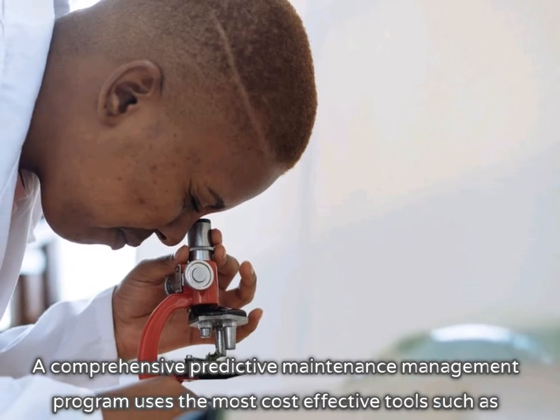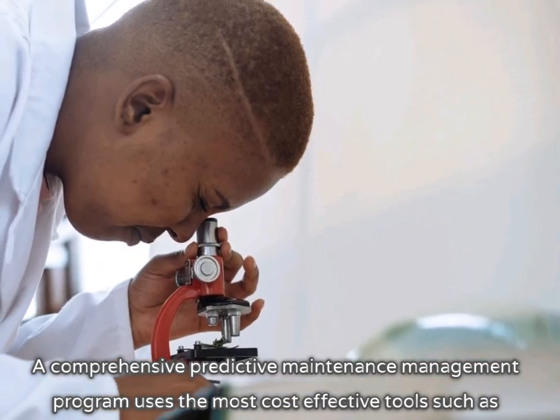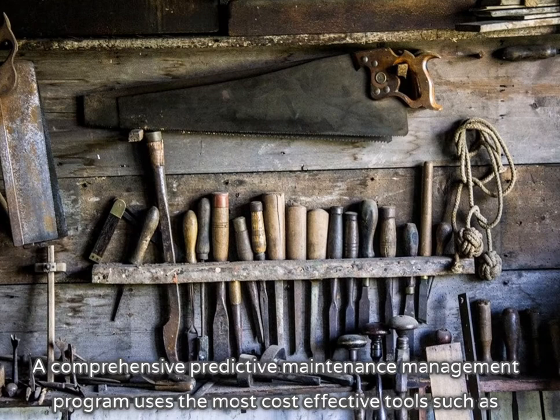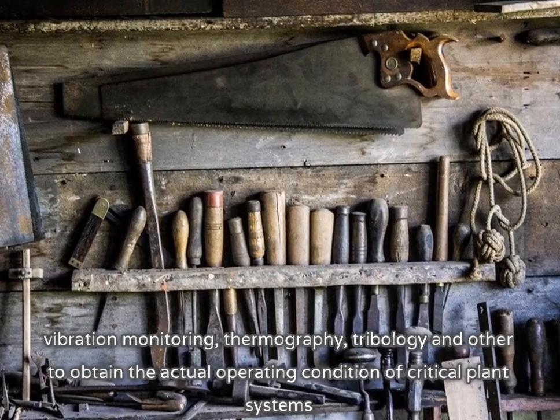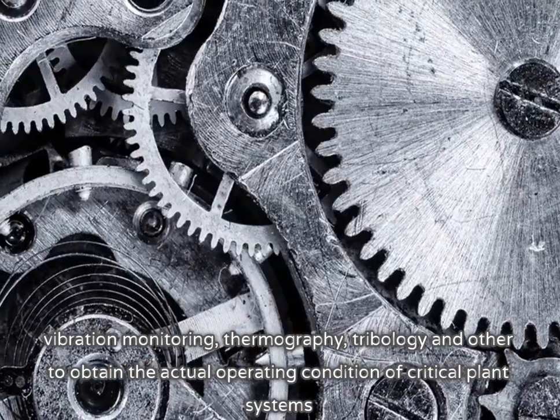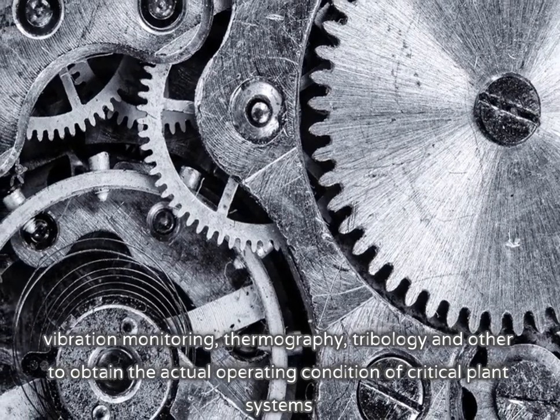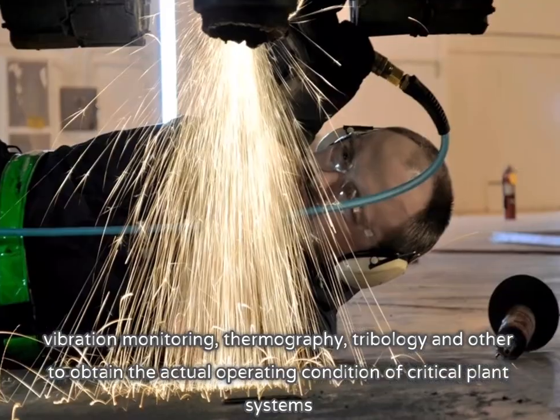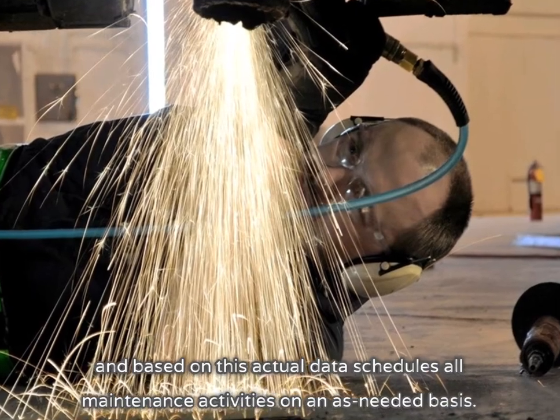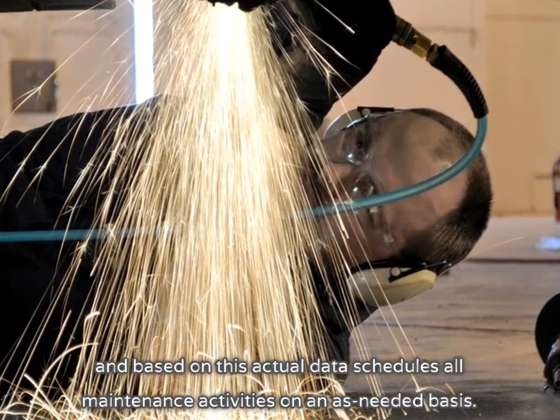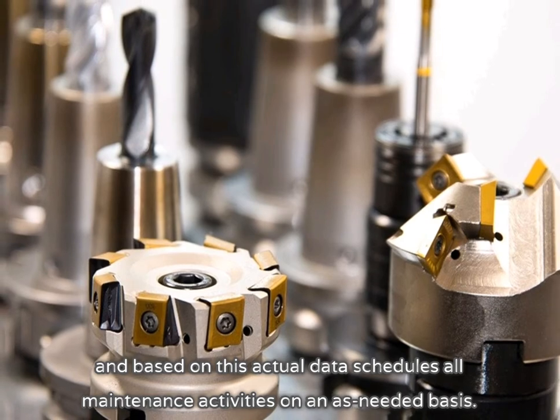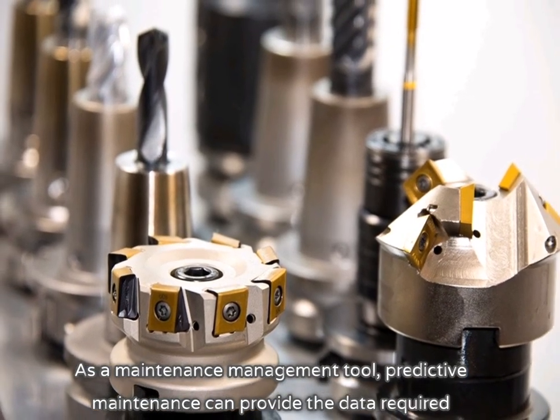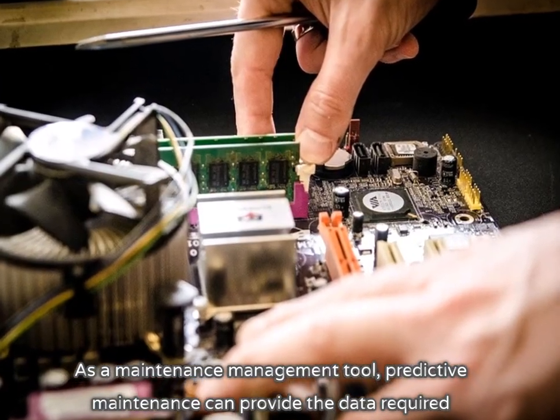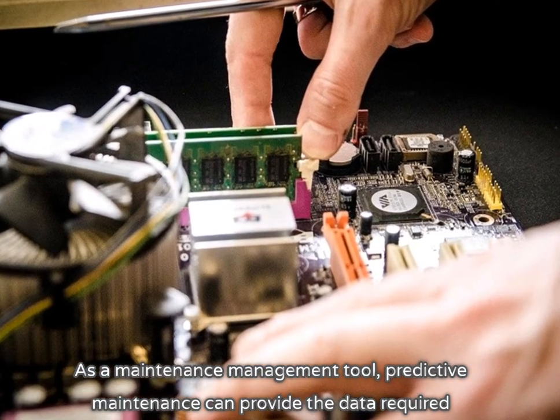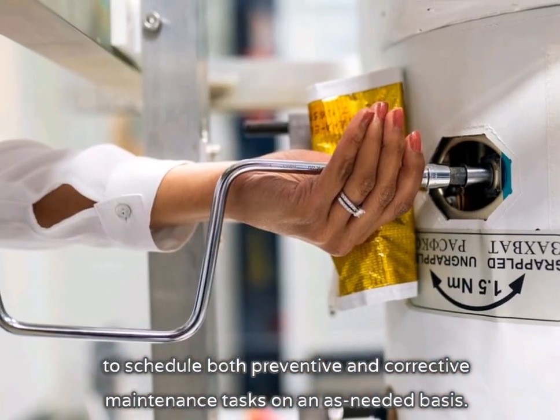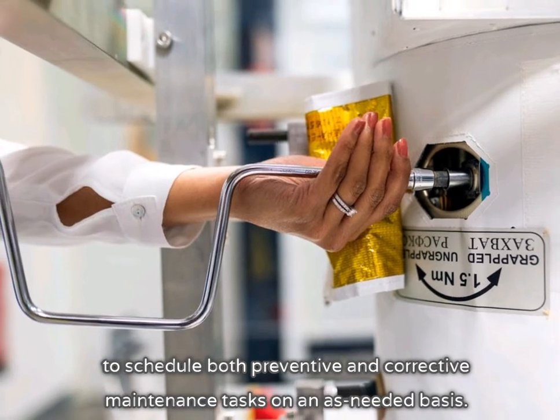A comprehensive predictive maintenance management program uses the most cost-effective tools such as vibration monitoring, thermography, tribology and others to obtain the actual operating condition of critical plant systems, and based on this actual data schedules all maintenance activities on an as-needed basis. As a maintenance management tool, predictive maintenance can provide the data required to schedule both preventive and corrective maintenance tasks on an as-needed basis.